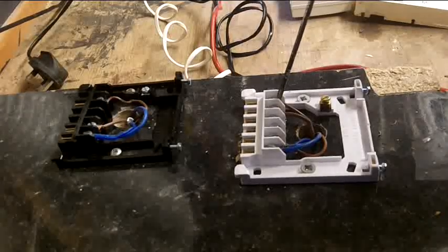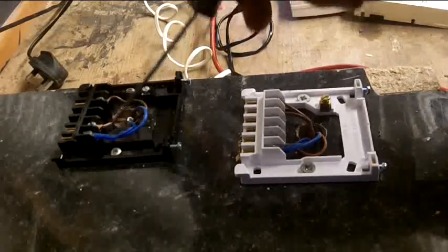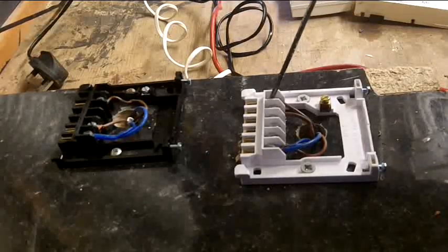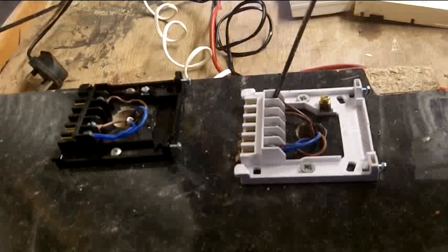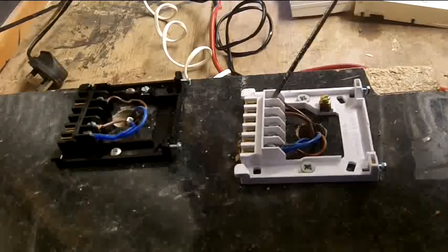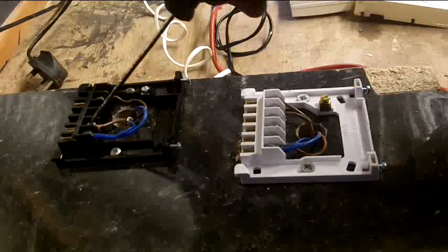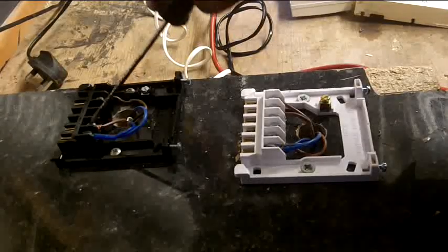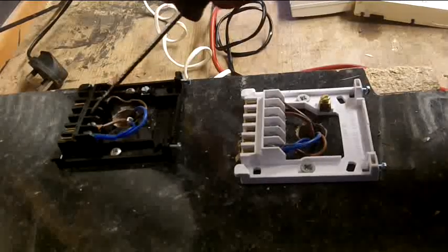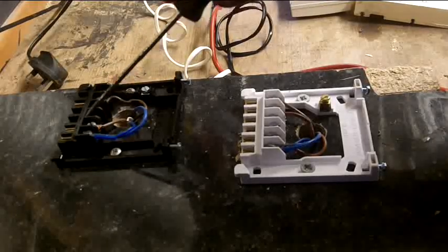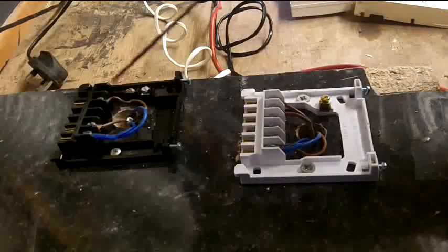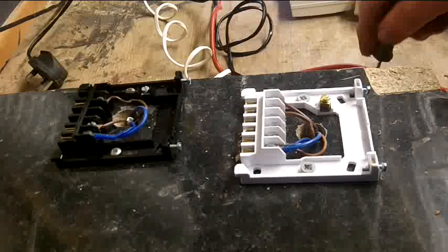That one is being broken by the thermostat. So that live, instead of going straight to the pump, it's going to the thermostat, to that line on the thermostat, that it's there in readiness, it's on standby until the temperature reaches, that flows a switch, then it'll connect that live to that live, and that's going straight to the pump.